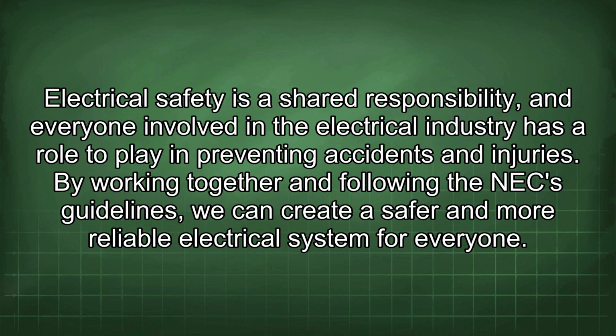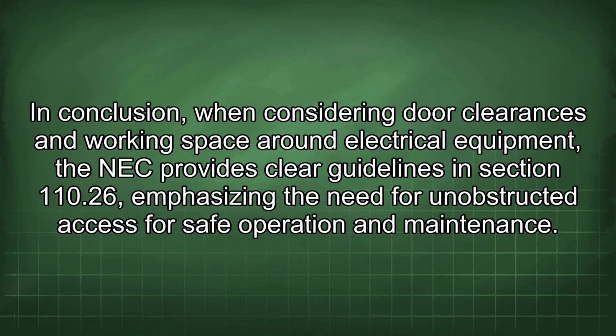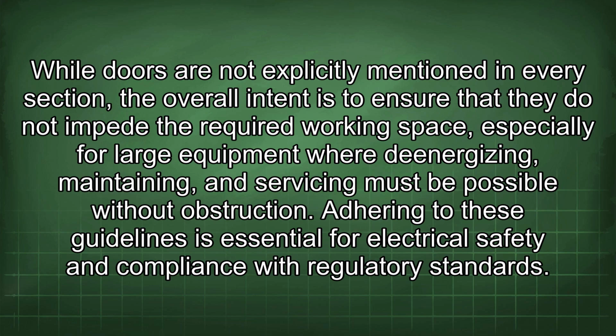In conclusion, when considering door clearances and working space around electrical equipment, the NEC provides clear guidelines in Section 110.26, emphasizing the need for unobstructed access for safe operation and maintenance. While doors are not explicitly mentioned in every section, the overall intent is to ensure that they do not impede the required working space, especially for large equipment where de-energizing, maintaining, and servicing must be possible without obstruction.